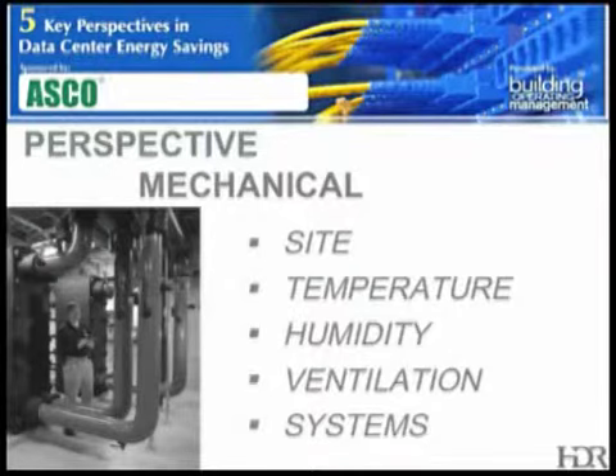I wanted to just touch on outside air for occupants. Of course, we're talking about minimally occupied facilities for the most part, so there really is not much of a need for ventilation to meet outside air for the occupants. I know questions have come up in the past about the need for increased ventilation for large crews that are doing the initial equipment installation, or perhaps a change out in equipment down the road. I would typically recommend that some sort of a temporary solution be applied if that was the case, renting some kind of a DX unit to provide that additional ventilation if it's really needed. Do not spend the capital to provide a ventilation system that's got that capability in it.